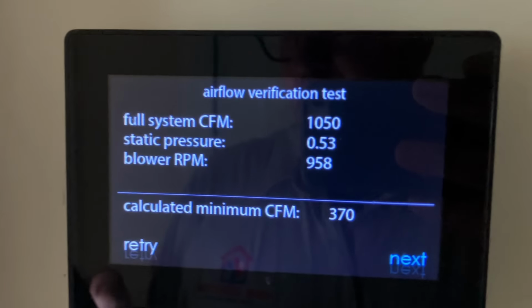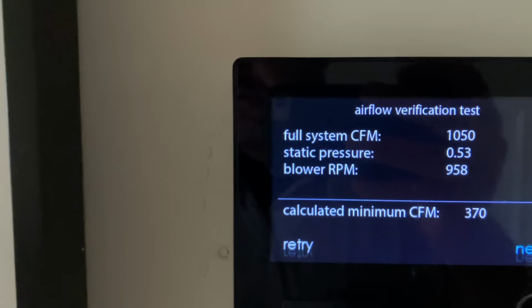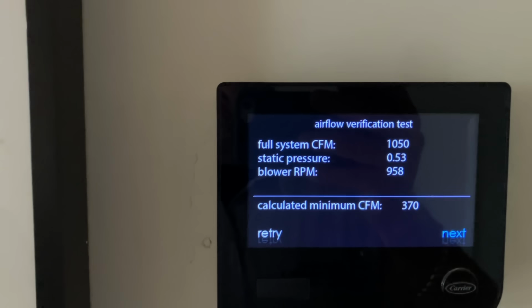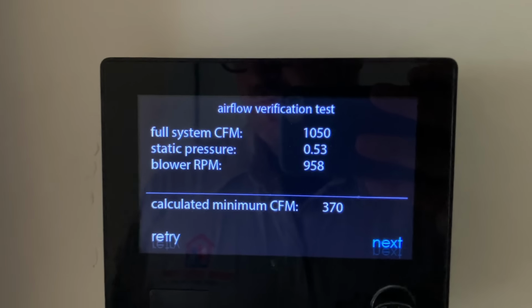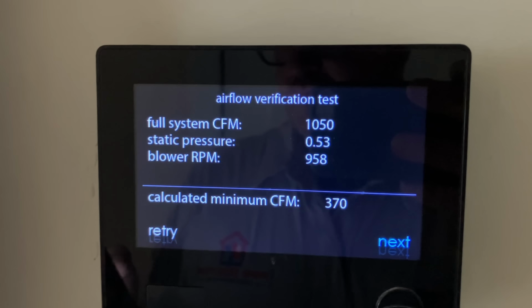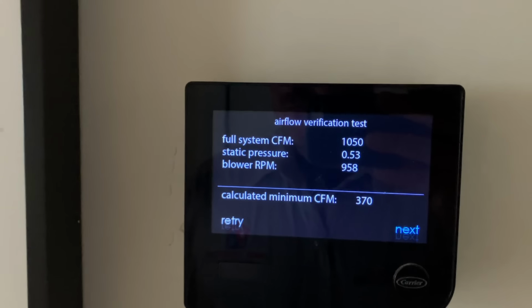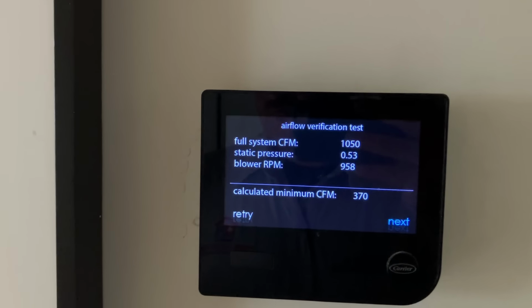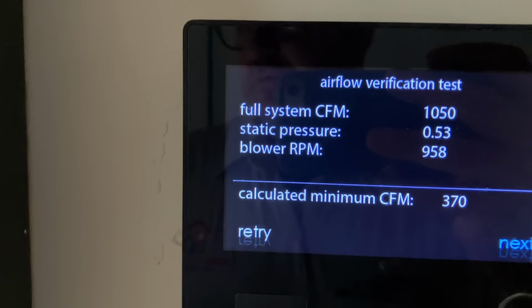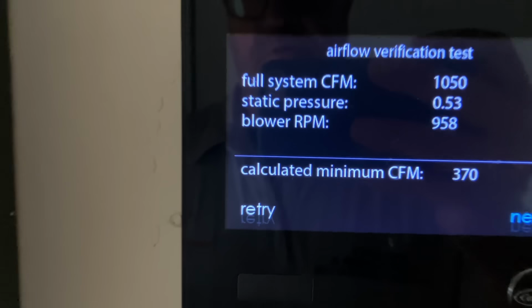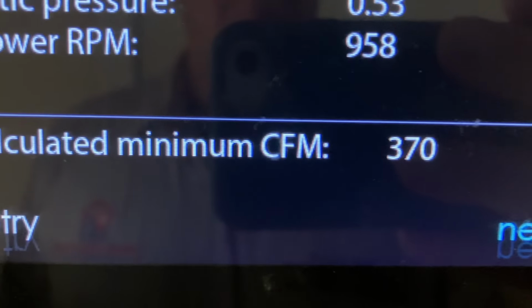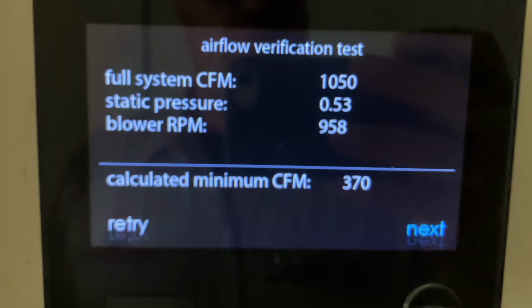Now, one thing I noticed here is that I would like to see the static pressure closer to 0.4. We have a brand new pleated filter and a clean coil. I checked all the diffusers, a couple of them were closed, so that may be the case. The homeowner had to run out, so we have to cut it short here.